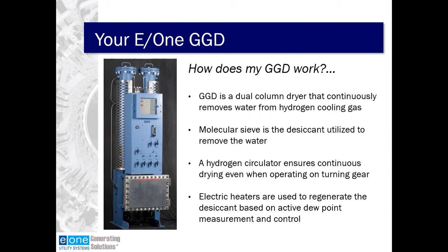So some systems out there may have a passive drying process, which relies on the rotor differential pressure to push the hydrogen gas through the gas dryer. Depending on the pipe work and the location of the dryer, the effectiveness of that flow will vary from plant to plant and even from day to day. The hydrogen circulator ensures that there's continuous drying at all times.